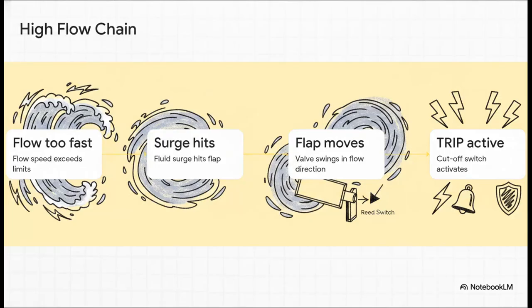The logic here is just brilliantly simple and incredibly robust. If the flow speed is too violent, the sheer kinetic energy of the oil forces that flap open. Bam! Just like the lower float, when this flap swings, it activates a cutoff reed switch, immediately sending a trip signal to shut the transformer down before it literally destroys itself.